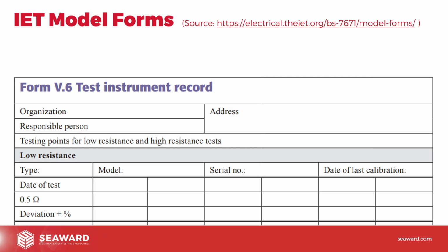And then the idea is that next time round you come and do it, you fill in the next column, you put the date in, 1st of August. So we go through, and you should be able to see if there are any changes, if anything's drifted or moved, because as long as you're using the same instrument and the same standard resistances, it should be there or thereabouts. You will naturally get variations for temperature and contact resistance and all the things we talked about before, but realistically you should get reasonable results. So this is our check for ongoing accuracy.